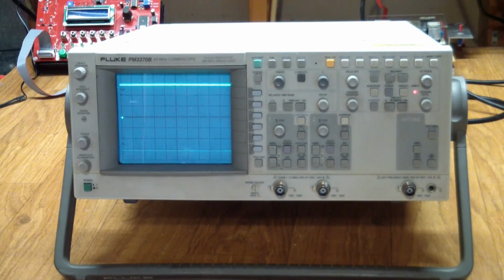If I turn up, oh, I guess I'm not supposed to turn any of these things while it's calibrating, so we'll find out if I messed up the calibration cycle here. But things seem to be running well. It's a neat scope, especially since it's dual mode, and I'm glad it got fixed. And I do hope that this will help you out if you ever fix a similar scope, or if you follow the general principles used in troubleshooting this and repairing this, and that should help you out on most any other scope too. The interesting part was that the problems were not only analog, but there was also logic problems with the DACs in here, which is fitting because it is a dual mode scope.